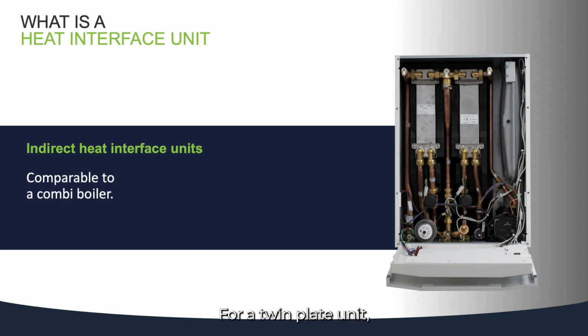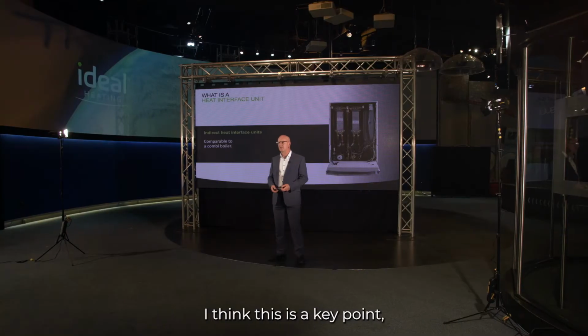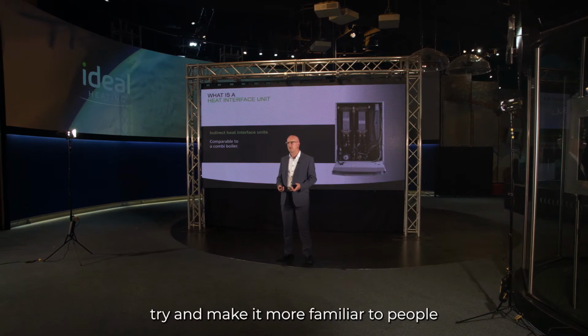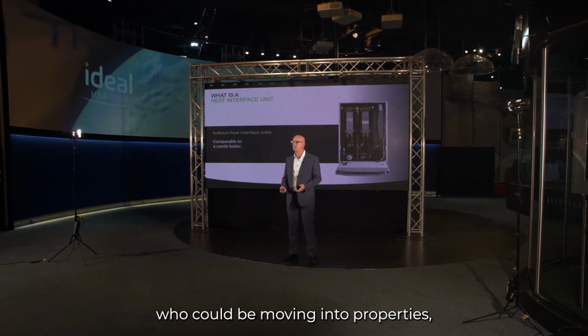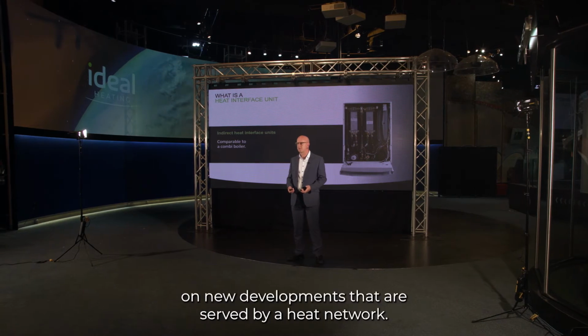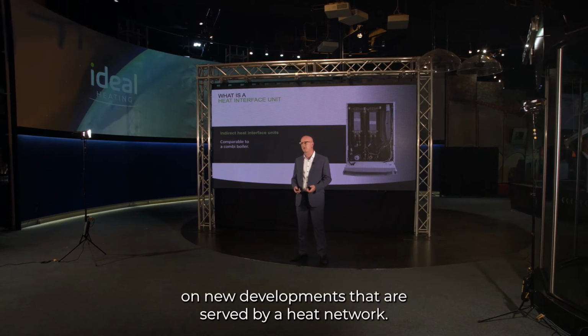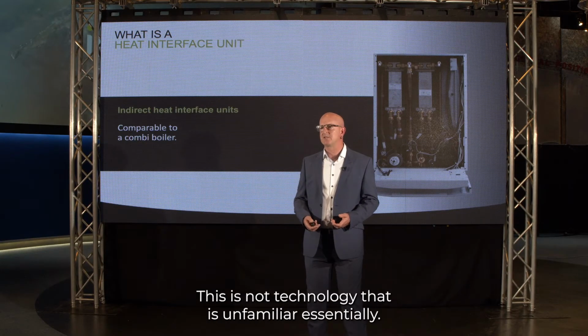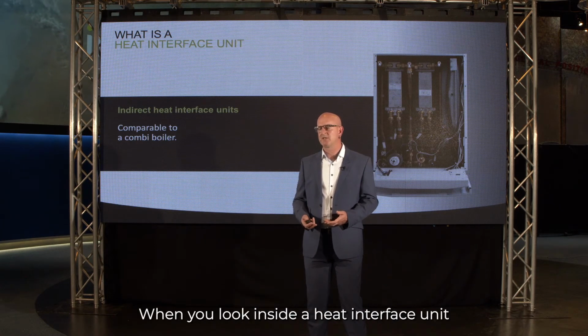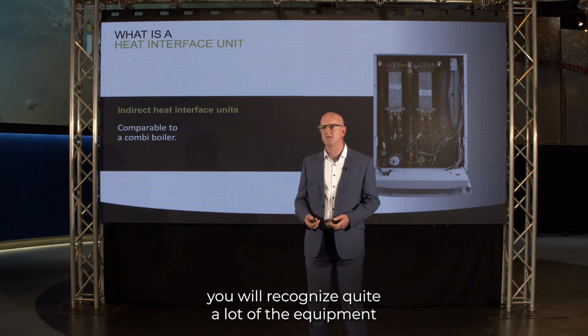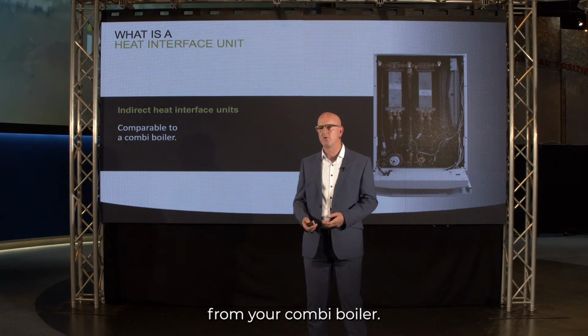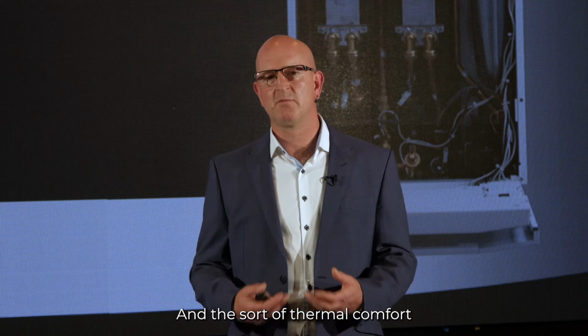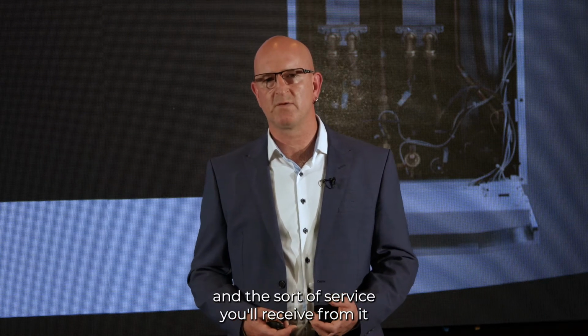For a twin plate unit where you have provision for heating and hot water from the HIU, these are comparable to a combi boiler. And I think this is a key point, try and make it more familiar to people who could be moving into properties or could be looking at buying properties on new developments that are served by a heat network. This is not technology that is unfamiliar essentially. When you look inside a heat interface unit, you will recognise quite a lot of the equipment from your combi boiler. And the sort of thermal comfort and the sort of service you'll receive from it is very much the same.